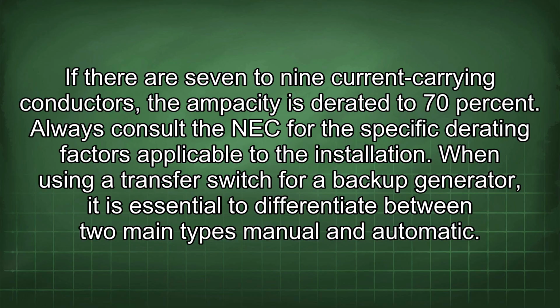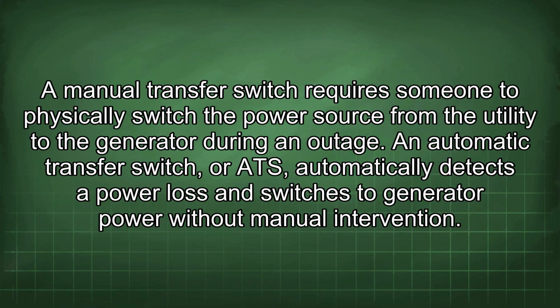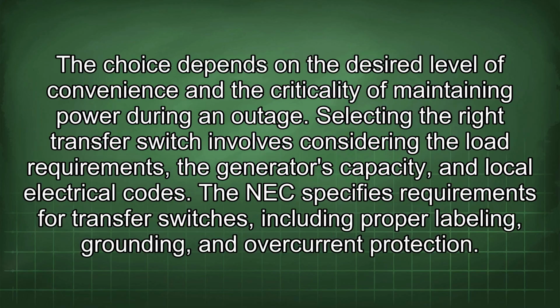When using a transfer switch for a backup generator, it is essential to differentiate between two main types, manual and automatic. A manual transfer switch requires someone to physically switch the power source from the utility to the generator during an outage. An automatic transfer switch, or ATS, automatically detects a power loss and switches to generator power without manual intervention. The choice depends on the desired level of convenience and the criticality of maintaining power during an outage.